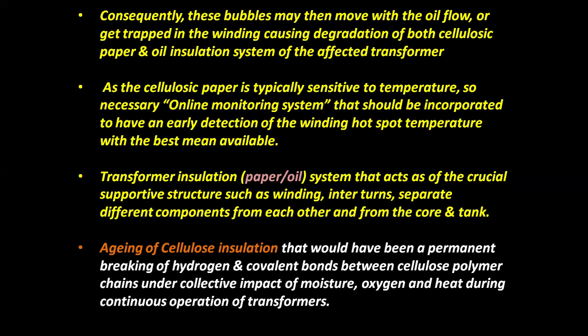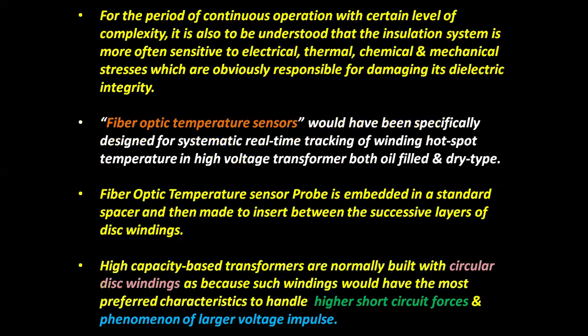Aging of cellulose insulation is a permanent breaking of hydrogen and covalent bonds between cellulose polymer chains under the collective impact of moisture, oxygen, and heat during continuous operation of transformers. For the period of continuous operation with a certain level of complexity, it is also to be understood that the insulation system is often sensitive to electrical, thermal, chemical, and mechanical stresses, which are obviously responsible for damaging its dielectric integrity.